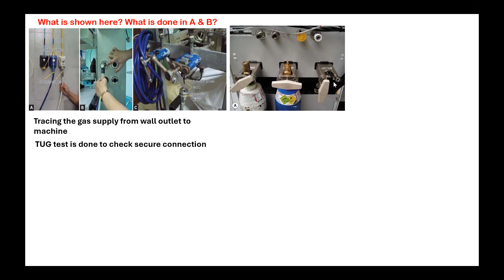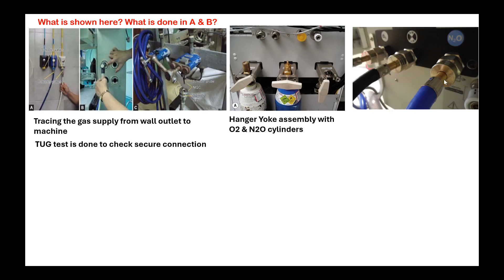It doesn't have a cylinder. Can it be left like this without a cylinder? A yoke block can be placed there. You have to place a yoke block. Fantastic. So oxygen and nitrous oxide are fitted into that, but we should never leave anything open like this. There is a yoke block. I will show you the picture later in one of the slides. And this is the back connection going into the machine.